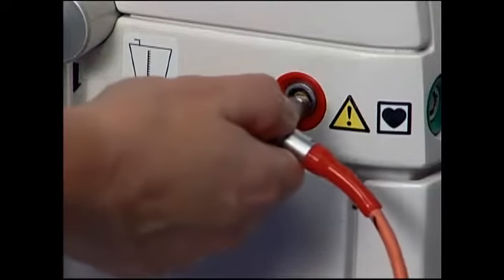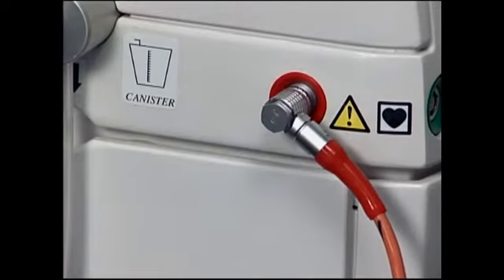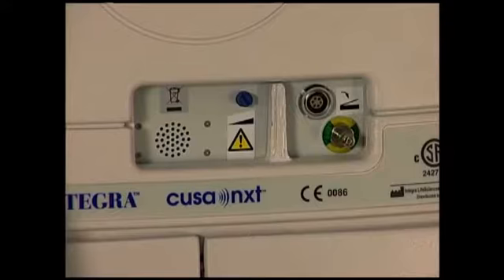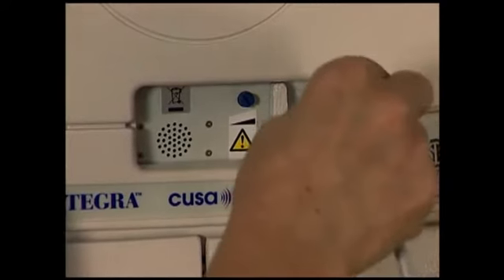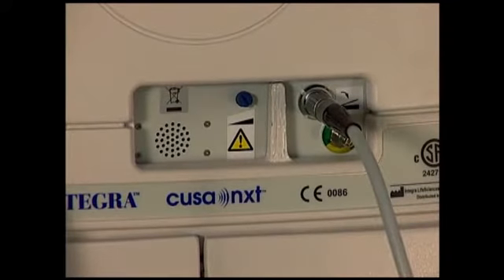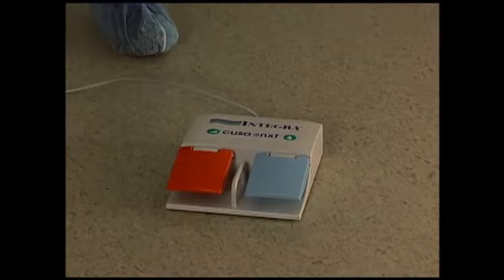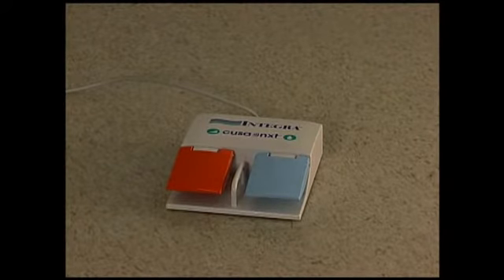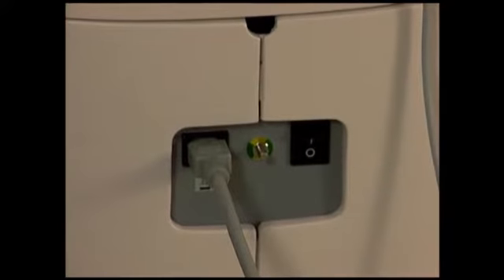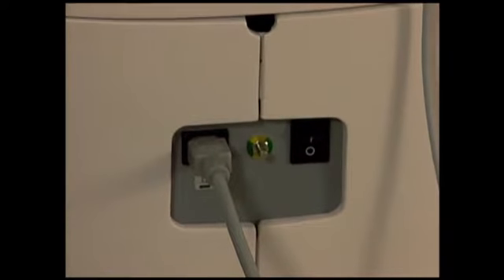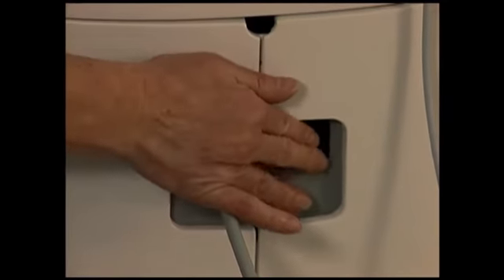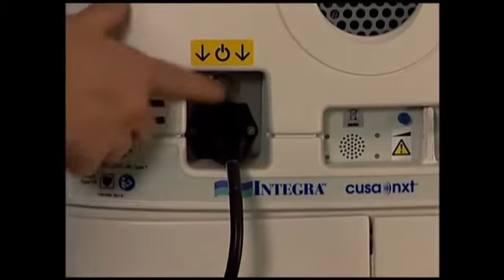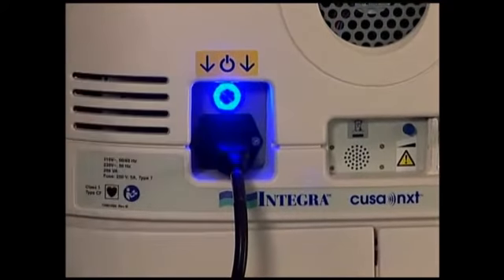Connect the handpiece plug to the color-coded port on the front or side of the console. Plug the foot switch into the foot switch socket located on the rear panel of the console. Place the foot switch in a convenient position for the surgeon. If using the service module, push the power switch on the rear of the service module. On the rear of the console, push the power button located in a recessed compartment above the power cord.